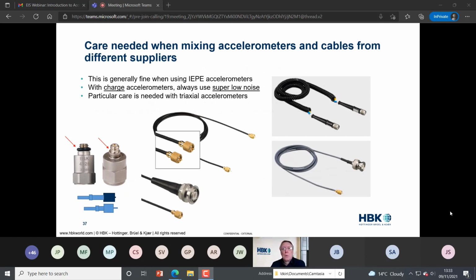Just another thing to watch: not all manufacturers' cables are necessarily directly compatible with other manufacturers' accelerometers. For example, some accelerometers have a rubber ring around the connector to ensure a good, sealed connection, whereas others do not. Depending upon the length of the fastening ring around the connector, you may or may not get a reliable continuous connection with the central pin.